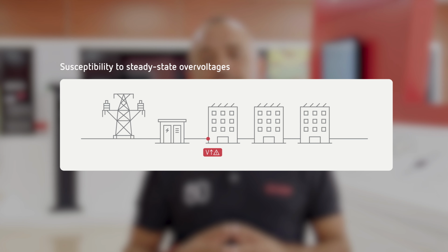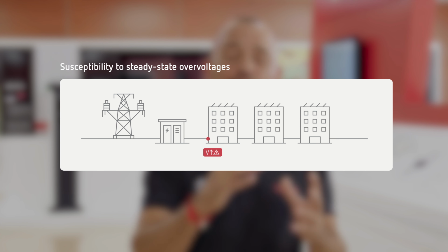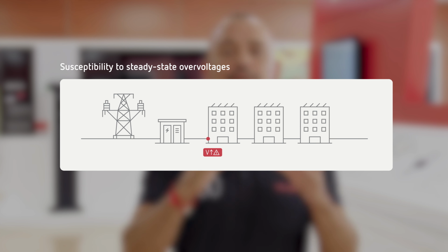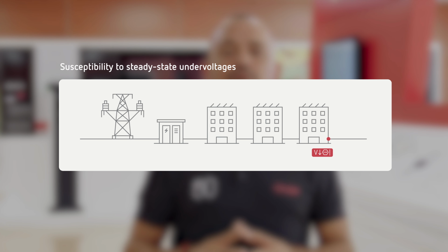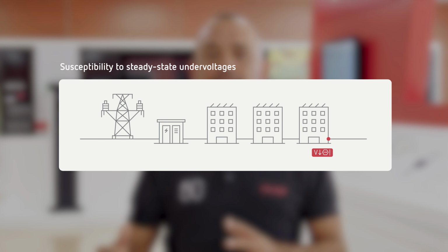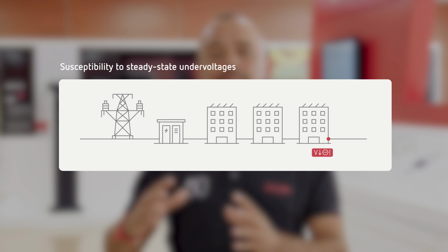As you can see, this standard is key to ensuring that the power supply is of high quality, reducing risks for connected equipment, and guaranteeing service continuity and efficiency in our installation. These recommended values are especially important if your installation is close to a substation, since you could have a high nominal voltage and easily experience over voltages, or when your installation is very far from the substation, as you could have a low nominal voltage and experience sags more easily.